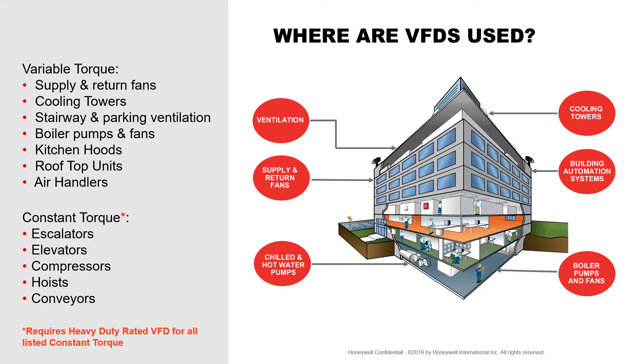Honeywell makes VFDs for HVAC applications — fans and pumps. These are applications with a fluctuating load, where we can ramp up or ramp down the speed of the motor to meet the load. These are called variable torque applications, and with them you will see energy savings with reduced motor speed.